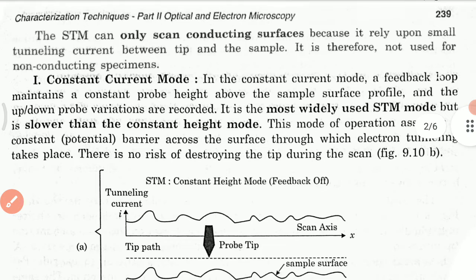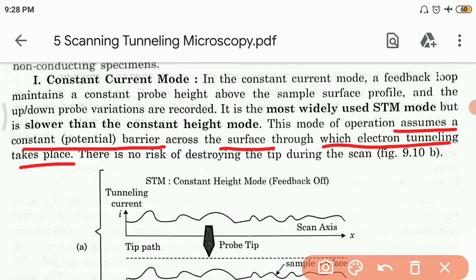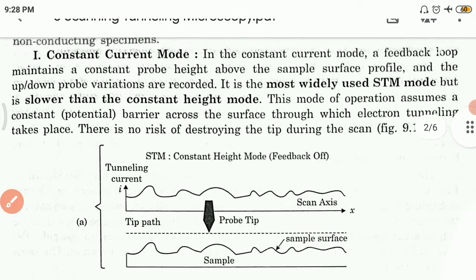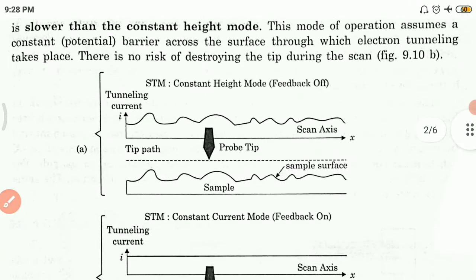Number one is the constant current mode. In this mode, a feedback loop maintains a constant probe height above the sample surface profile, and the up or down probe variations are recorded. It is actually the most widely used STM mode, but it is comparatively slower than the constant height mode. This mode of operation assumes a constant potential barrier across the surface through which the electron tunneling takes place, and there is no risk of destroying the tip during the scan. So in this mode there is no risk of tip destruction in the scanning process.